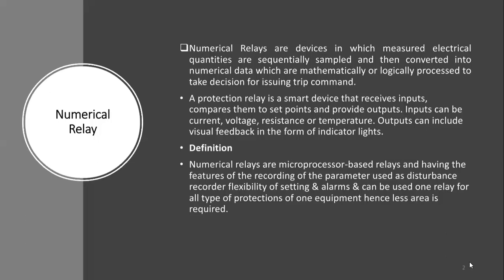Numerical relays are those devices in which measured electrical quantities are sequentially sampled. Whatever the incoming electrical quantity — for example, in any circuit we have a current transformer (CT) — the signal we get will be in analog form. Current and voltage signals will be in analog form. First of all, we will pass them through a low-pass filter, and then we convert them using an ADC — Analog to Digital Converter.